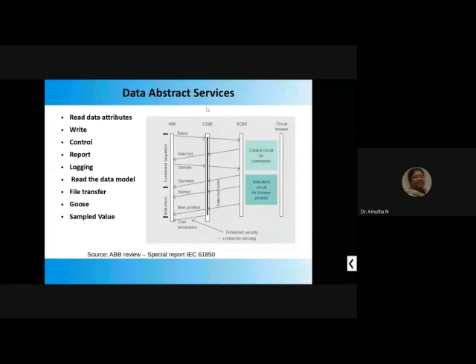In case of a microcontroller or microprocessor, we may have three types of communication: read data, write data, and control data. Whereas in IEC 61850, we have other data types too. Apart from read data, write data, control data, we have report data—report meaning it reports events happening in that particular model. Also logging, reading the data model itself, file transfer, GOOSE, and sample value. GOOSE and sample value are the important messaging services of this relay.